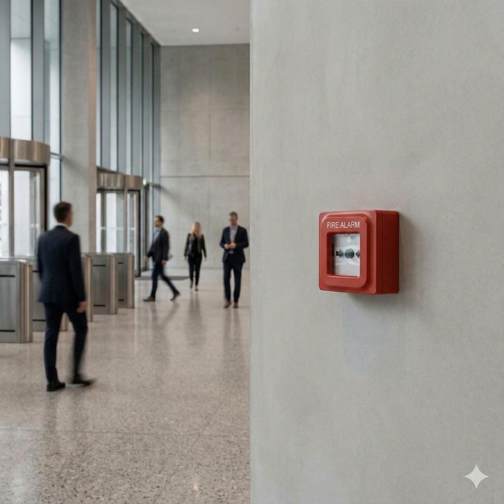And for high-rise buildings, it's even longer. Significantly, sometimes jumping to 60 hours of standby, reflecting the greater complexity and time needed for a high-rise evacuation. But here's the critical check that often fails in the real world. Batteries degrade. How do you ensure a battery that's been sitting for months can actually perform?